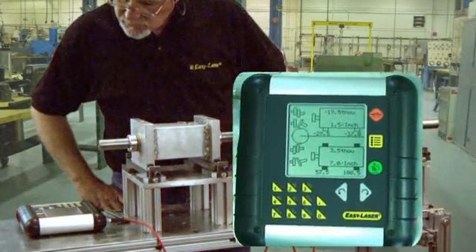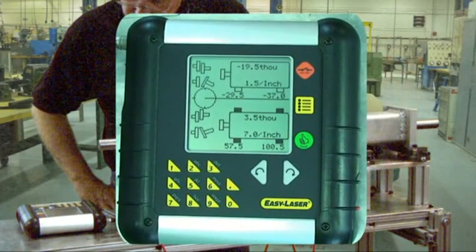We can now see the measurement results. The top part of the screen is the vertical plane and we can only see 2 feet which means we have to lift or lower the machine in this plane. The lower part of the screen is the horizontal plane and we are looking straight down on it so we can see all 4 feet. This means we slide the machine left or right to align.